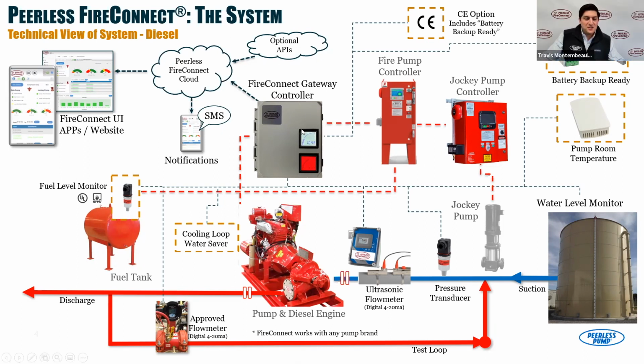Absolutely, it goes outwards. We can take all of this data and send it to wherever is required, whether you want to integrate it into your building management system because you want to see specific components, or into an ITM platform like InspectPoint, for example. We talk about reading that gauge value, right? We're monitoring suction pressure, jockey pump starts, system pressure. So when you're doing your weekly or monthly walkthroughs and you've got that ITM report, why do you have to walk to the pump room to look at the gauge to make sure you've got sufficient suction pressure? Let that field already be completed in the ITM sheet. So that data can be sent outwards as well.